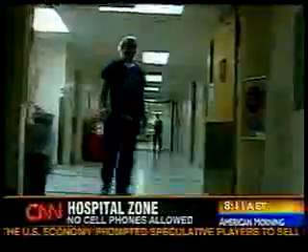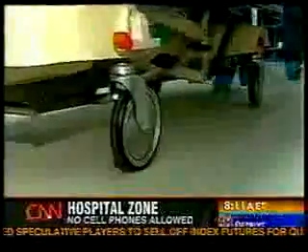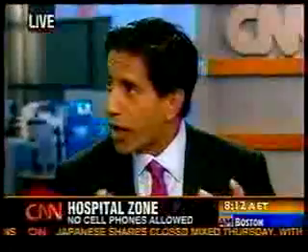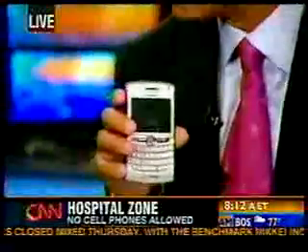Isn't a ventilator something with a hard switch on it? Yeah, you'd think. I mean, I'm not sure what the signal is, if somehow it's interfering with the signal somewhere, but it actually sent a signal to the mechanical ventilator and turned it off. And basically what they did was they just held these phones within 3 feet away. They weren't even talking on them, just holding them on and seeing what kind of electromagnetic interference it was causing.